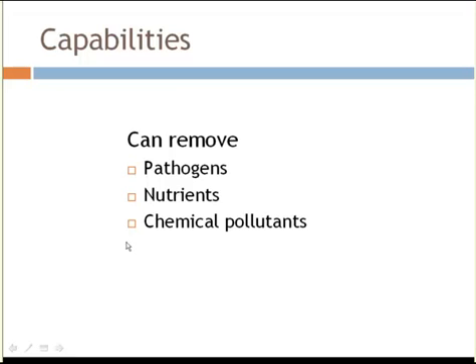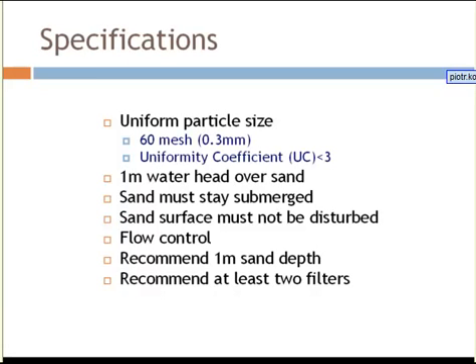A collaborator here on campus in the Department of Civil and Environmental Engineering, whose specialty is sand filtration systems, has identified sand filters as removing pollutants such as MTBEs, fuel additives, and gasoline, for example. As for what comprises a slow sand filter, the sand itself is the key. The sand grains must be of uniform size and rounded — sharp sand can pack and restrict water flow. A 60-mesh sand is ideal, that's about a 0.3 millimeter diameter grain. We use sandblasting sand because it's very uniform, and uniformity is key to good performance in the sand filter.